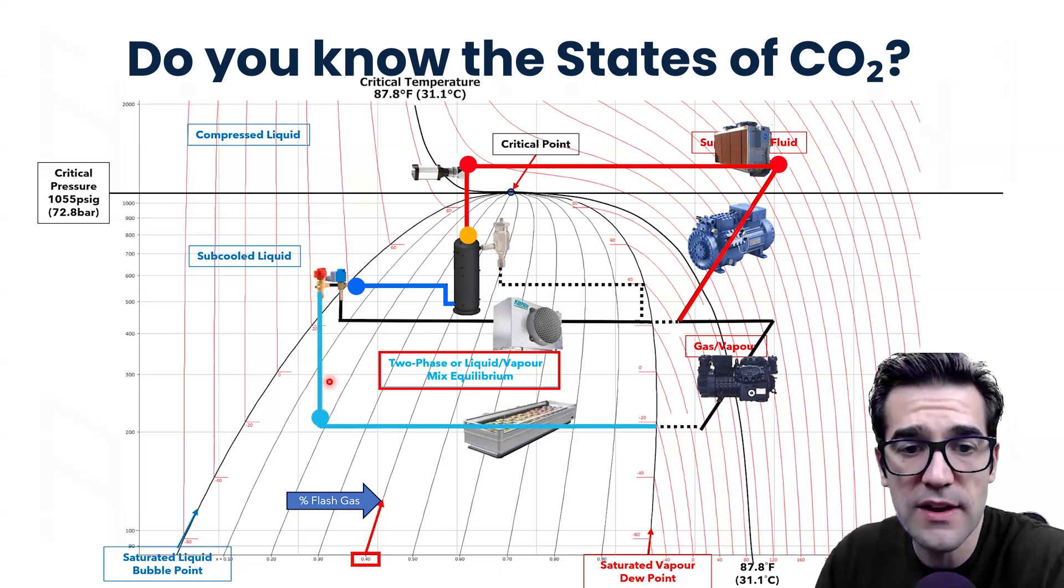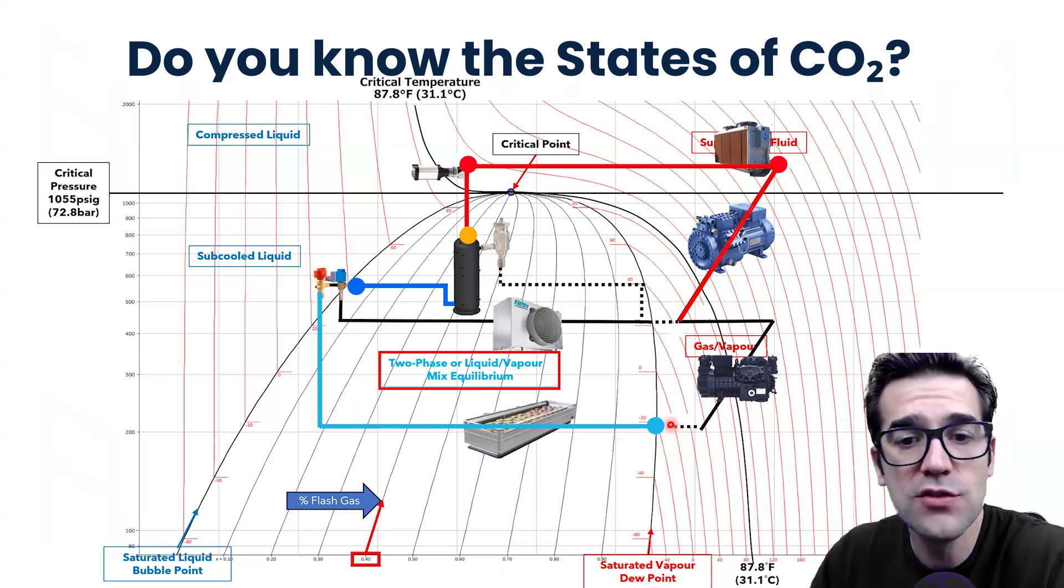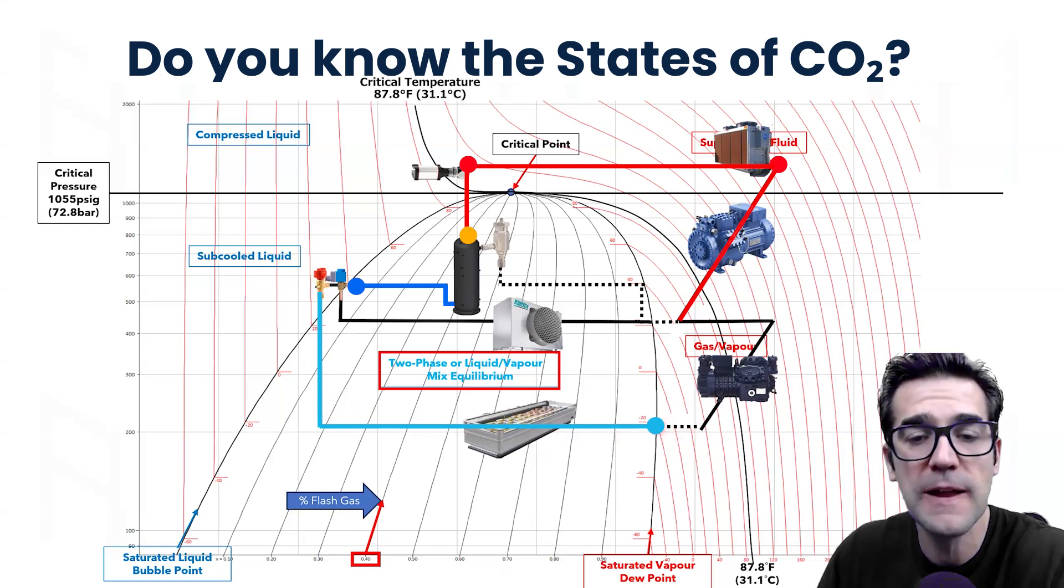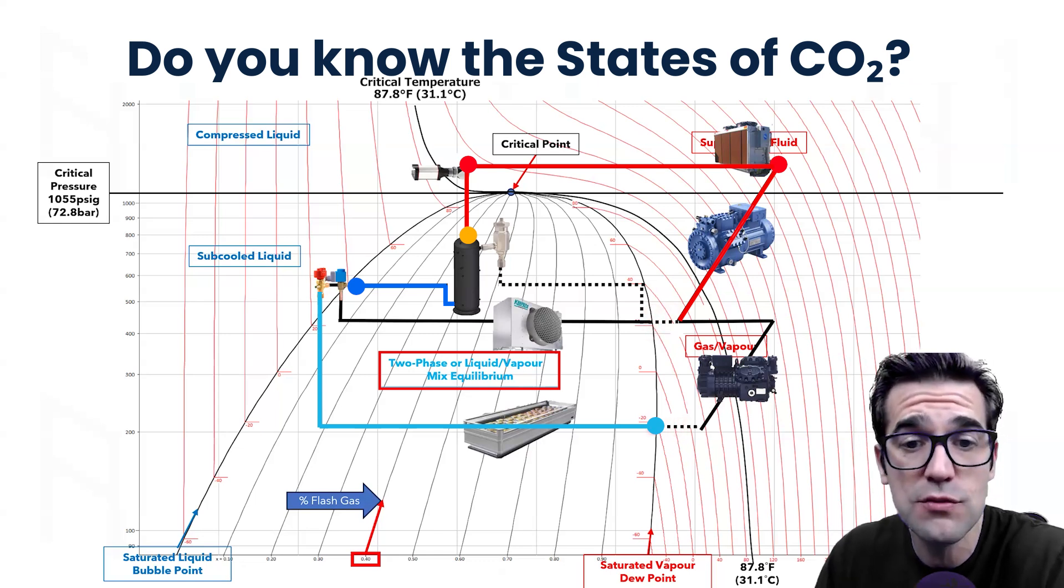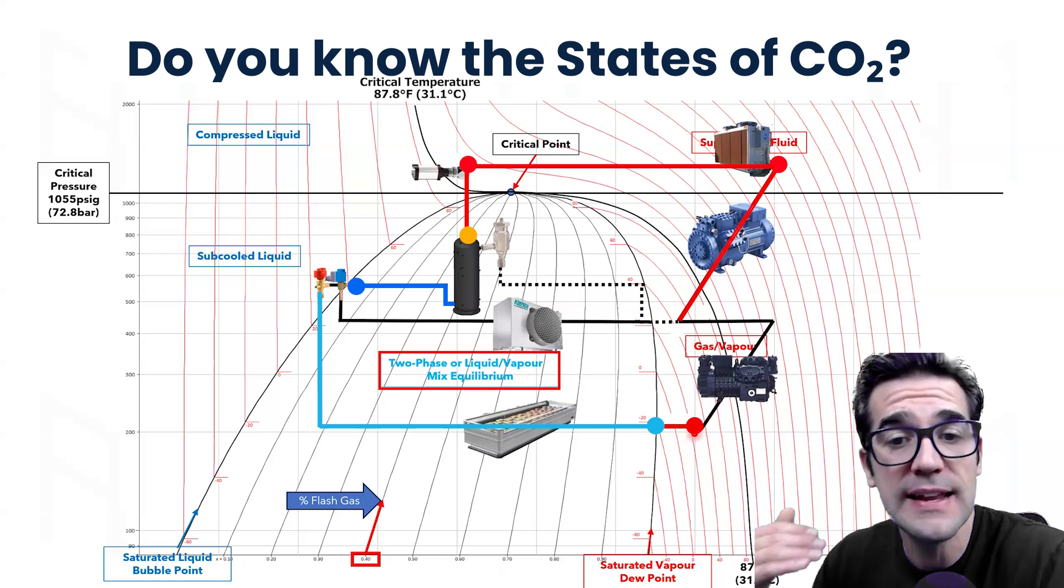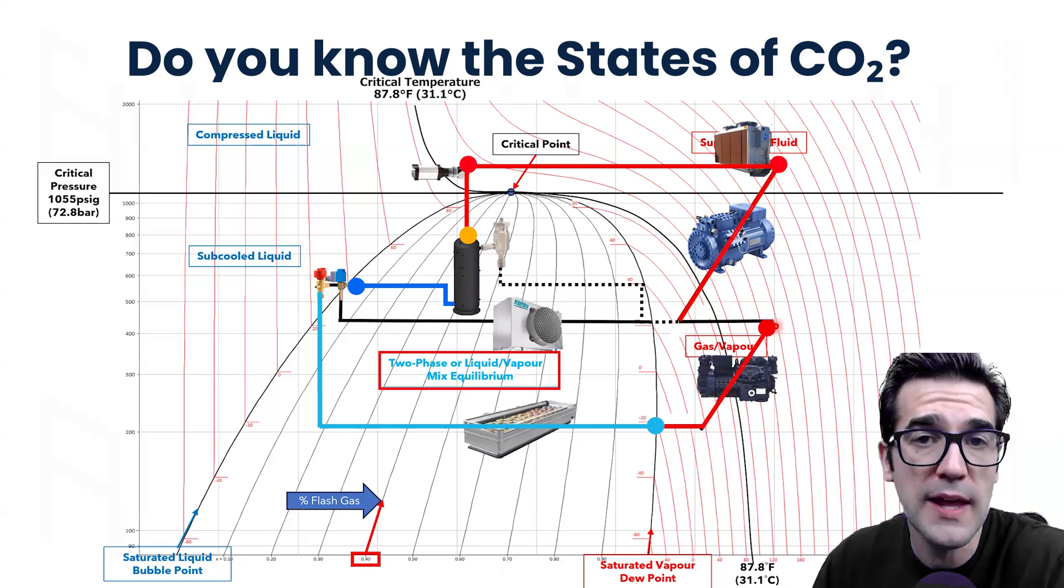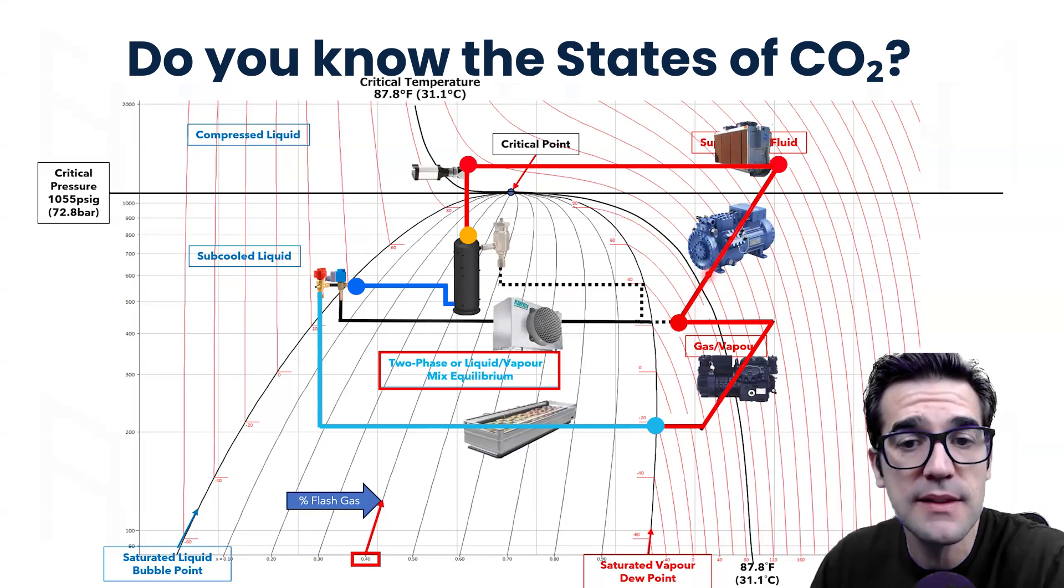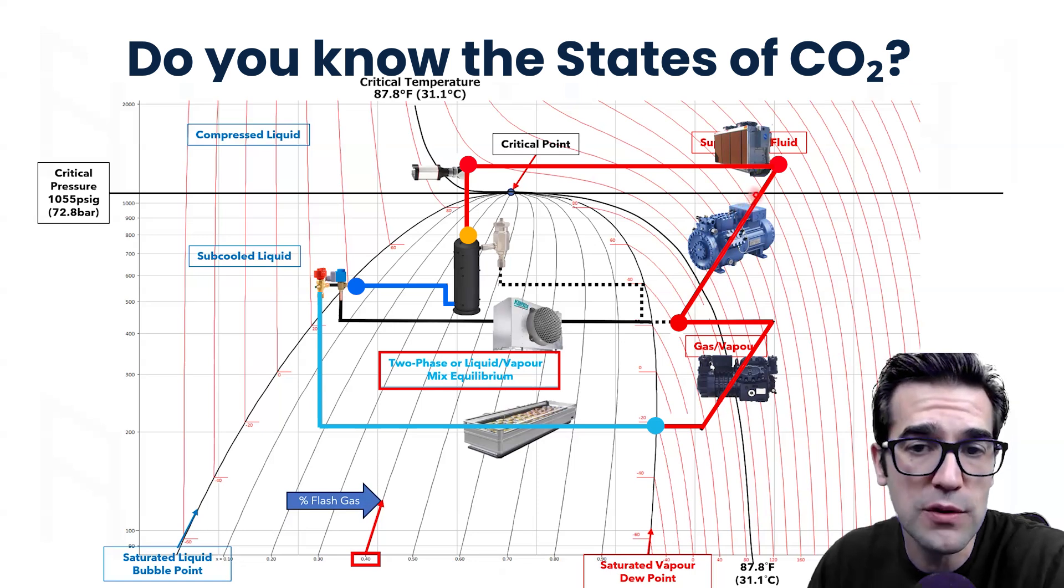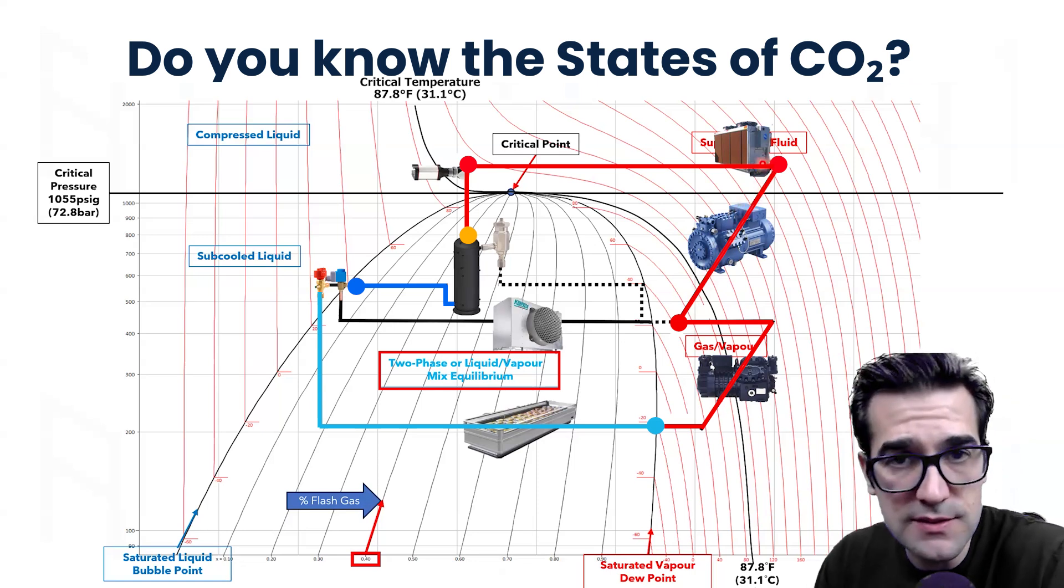As we go down and across, then we get back over to our saturated vapor or dew point line. So we make sure we do not have wet gas going back to each of the compressors. We need to have superheat going back to them. Now we're back into that gas vapor CO2 as we travel through the low temp booster compressor. And then we are a supercritical fluid leaving that compressor up to the gas cooler. This is how it's done.